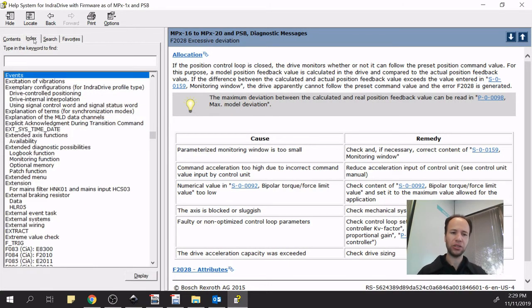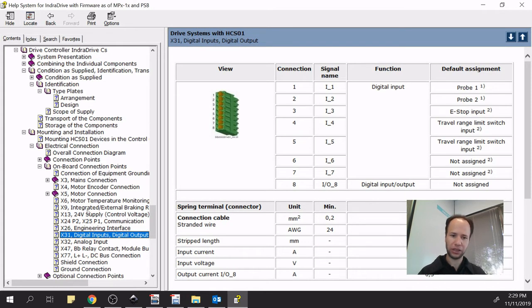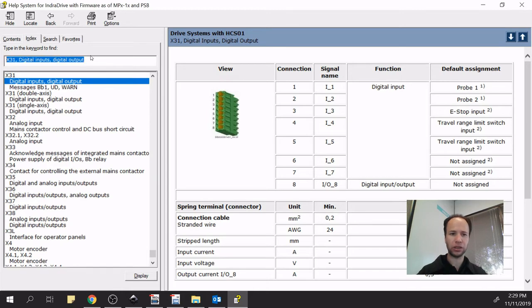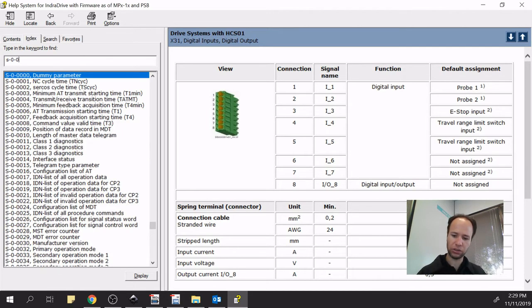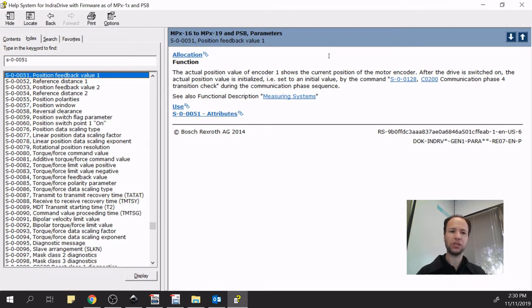Besides faults, we can find additional hardware information — for example, IndraDrive X31, which is a digital input connection on the IndraDrive itself. You can double-click and use Locate to see exactly where it is. The same applies to parameters — for example, S-0-0051, which is position feedback. Everything you can find under our PDF manuals is available inside IndraWorks. So before wasting time searching PDFs, I would strongly suggest using the help file search inside IndraWorks.